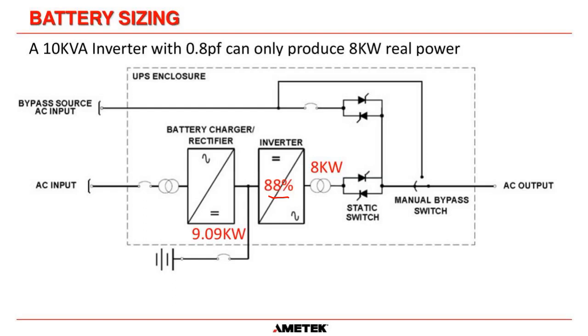So we're saying for an 8 kilowatt output on our inverter, if the inverter is 88% efficient, you divide 8 kilowatts by 0.88, which means we need 9.09 kilowatts of power on the DC side to produce 8 kilowatts of power on the AC side. Now, we need to know the DC side because that's where the battery is connected. So hopefully you can follow me through this. That's the important number here, 9.09 kilowatts.